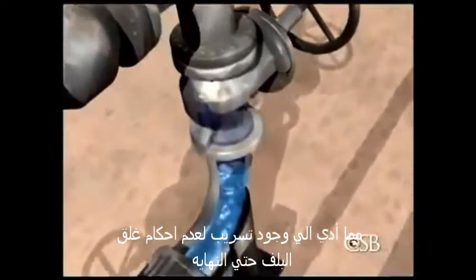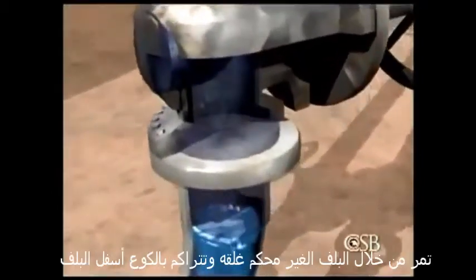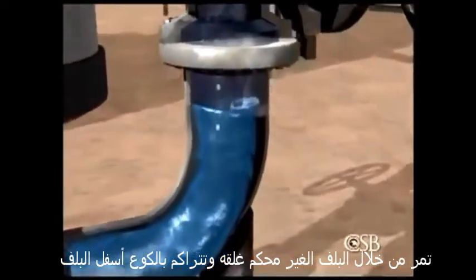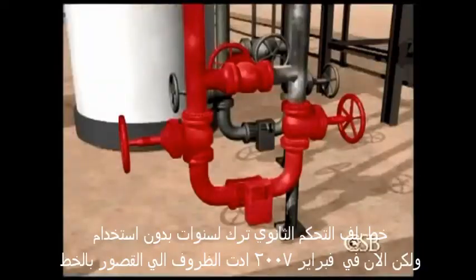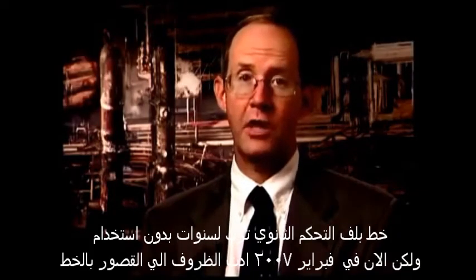The propane above the valve contained small amounts of water. Some of the water, which is heavier than propane, sank through the valve and accumulated in the piping elbow below. The piping dead leg formed by the mixed control station had been left connected for years, apparently without incident.